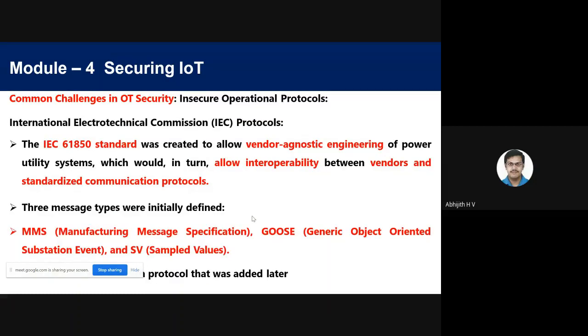Then there are certain protocols developed by IEC, the International Electrotechnical Commission. They have defined certain message types, for example MMS, that is Manufacturing Message Specification; GOOSE, that is Generic Object Oriented Substation Event; and SV, the Sampled Values Protocol.